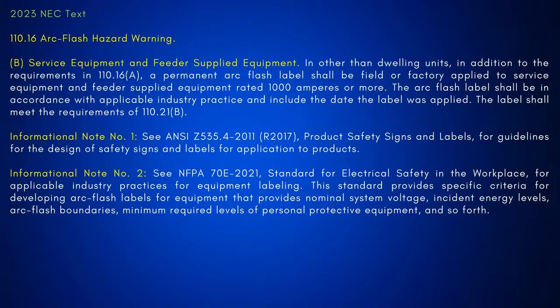All right. Then if you look at B, it says in other than dwelling units, and it talks about in addition to the requirements of 110.16(A), and this is where the feeder and equipment is over what? 1,000 amps or more. Then you have to start looking at a few things here, and look where it goes down, and you pick up informational note number 1. There's your ANSI standard, and informational note number 2 takes you to where?